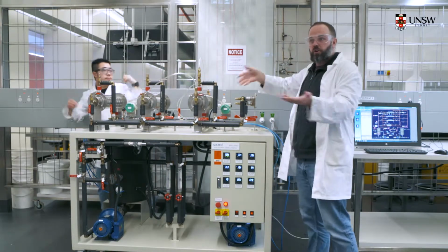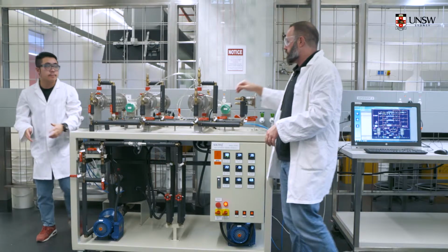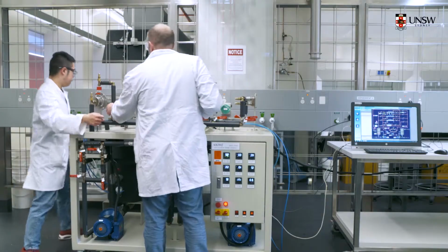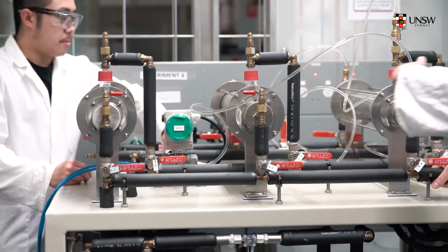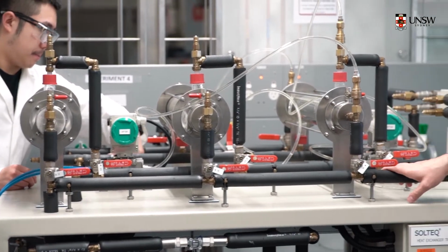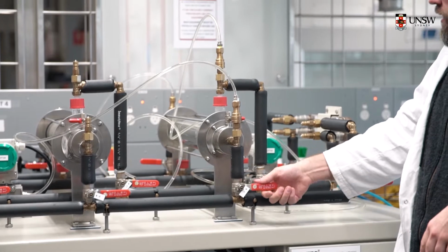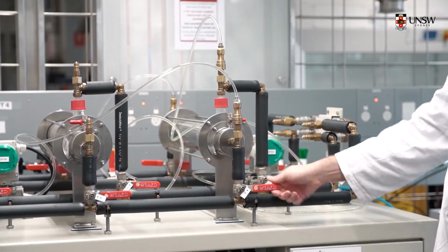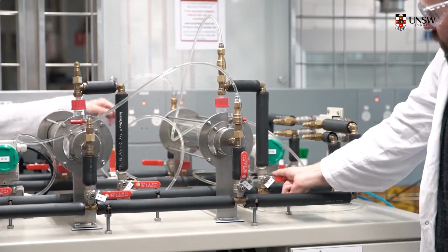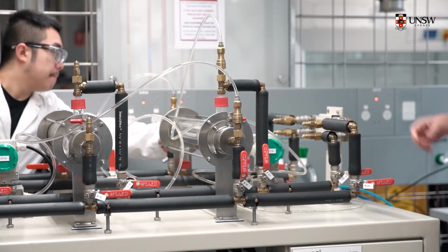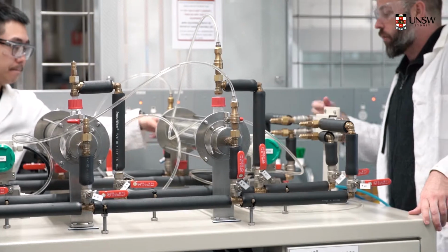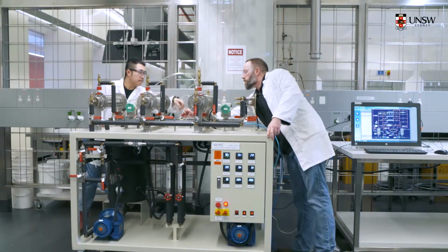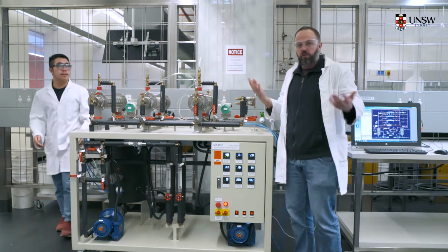Okay, so that's how you go from one heat exchanger to the other in terms of switching out the pressure lines. When you do that, you want to close off the valve so no water is flowing through that particular heat exchanger, and then open the valves to the heat exchanger you're about ready to measure. Right now this valve is closed. You want to open that up for the hot water, open it up for the cold water, and likewise in the back, open up the outlets for both the hot and cold. Actually, it's this one. And that's how you do that.